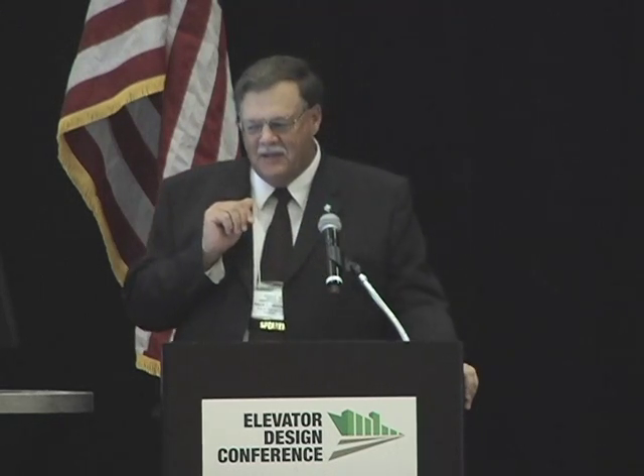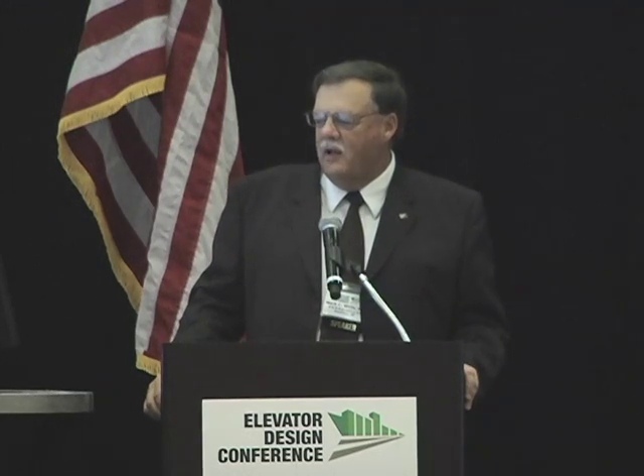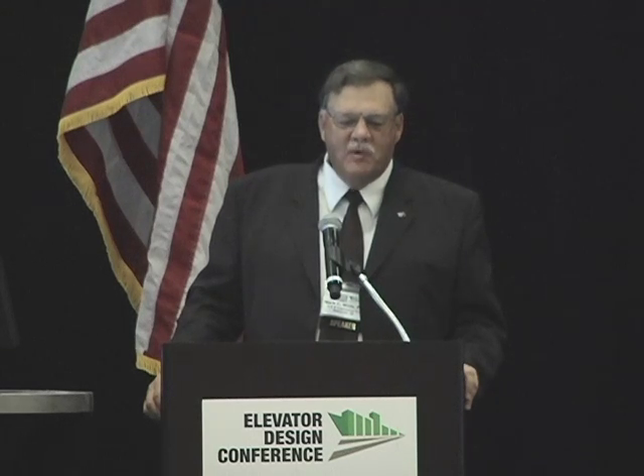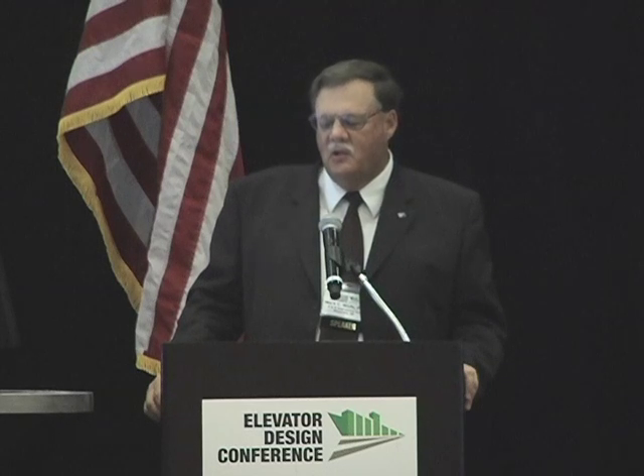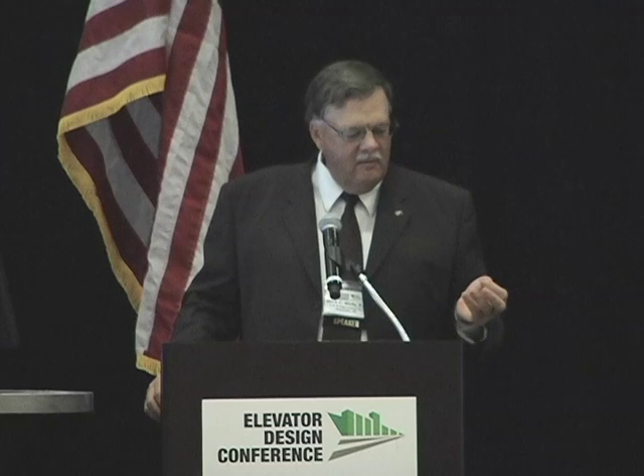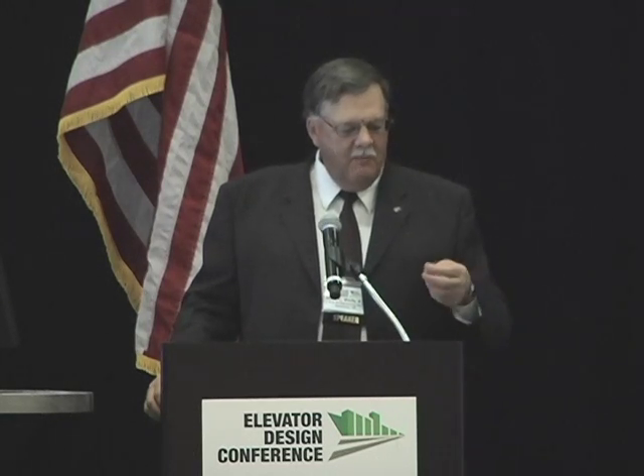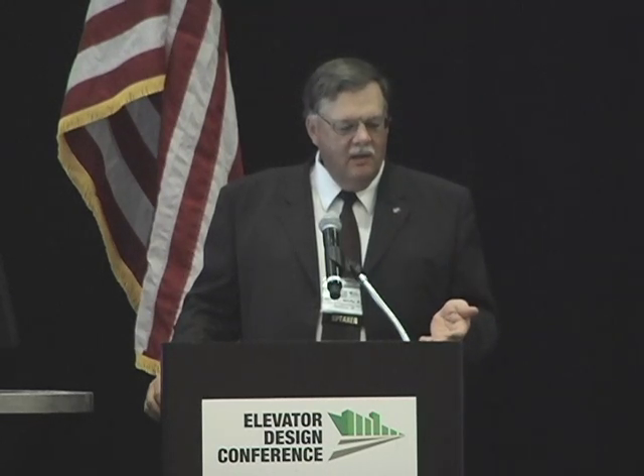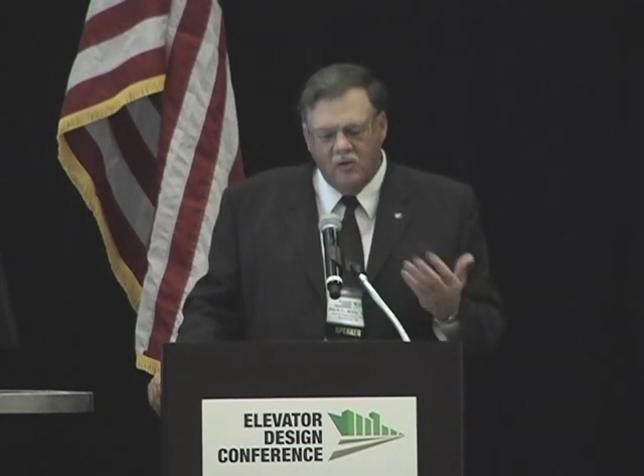But there are some interests, and sometimes in standby, if you have any standby generators or generation, we have some utility in Oregon that's doing a distributed generation sharing, where if you have a large standby generator, they will come in and put in equipment so they can bring that generator online to reduce your load and make it like a generation source out on the grid. And they will do all your maintenance, buy all your fuel, and keep up that generator for you just so that they can have access to it, and it gives them some peak shaving capability on the power grid. So sometimes there's opportunities to actually do a partnering agreement with your power service provider to make your generator available as a peak shaving generator into the power grid, and that's a place where you can have some opportunities economically to pay for that.